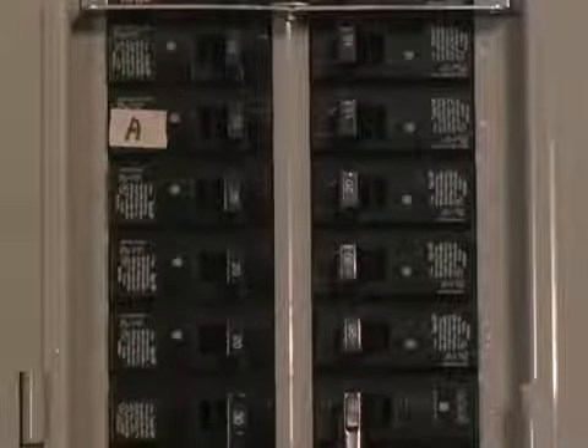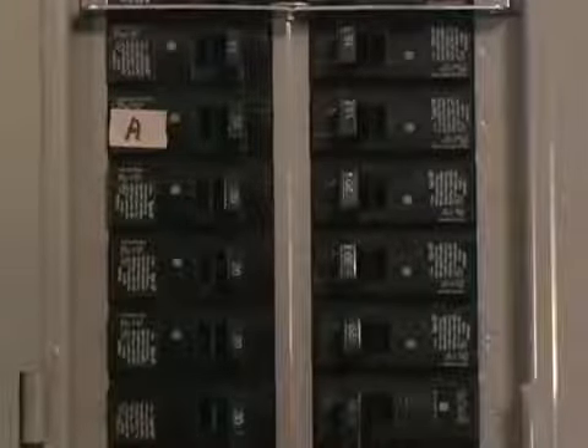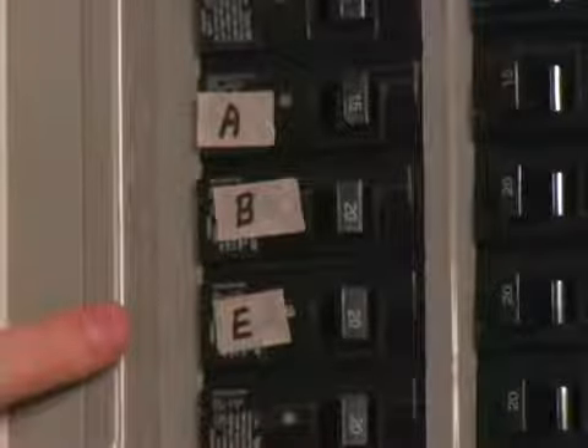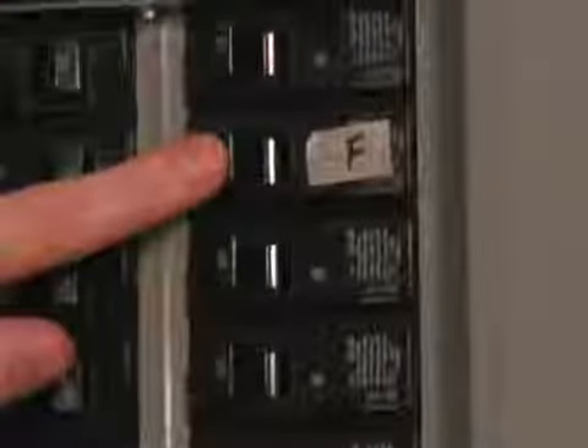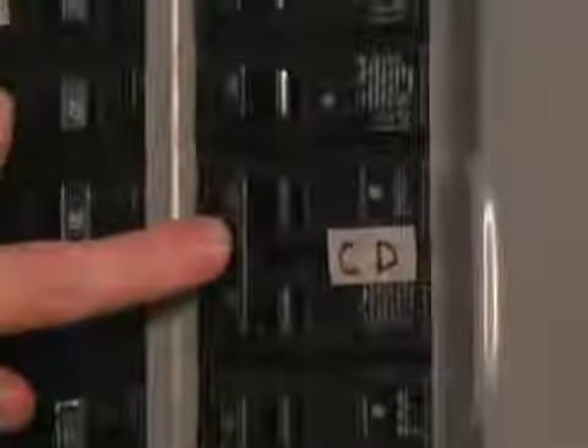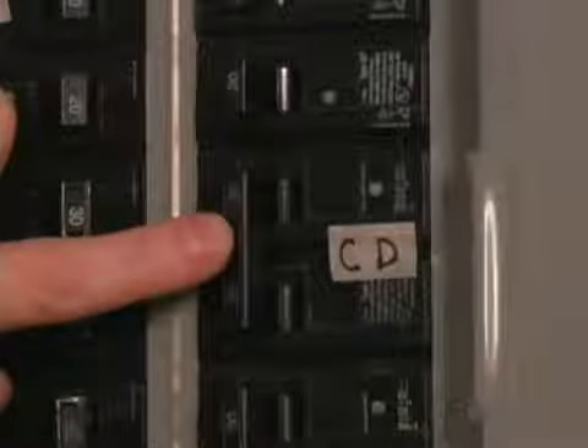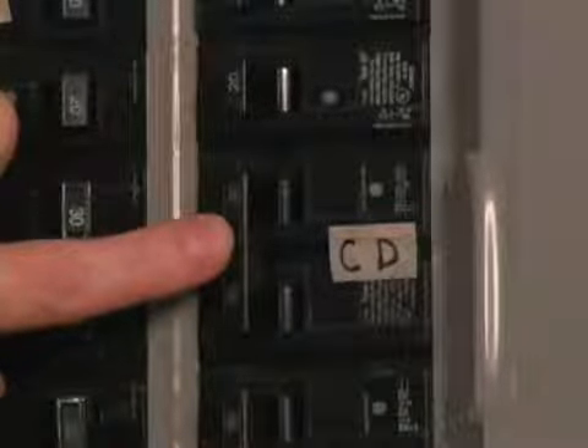The next appliance I'd like to power is the refrigerator. In this panel, it's on the kitchen circuit, which is number 9. I've now finished labeling the circuit breakers. We've chosen also to power the sump pump, living room lights, and well pump. Note that the well pump is on a double pole circuit breaker and will be powered by transfer switch circuits C and D.